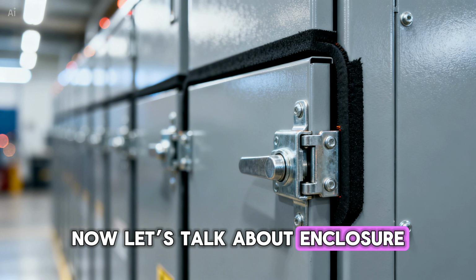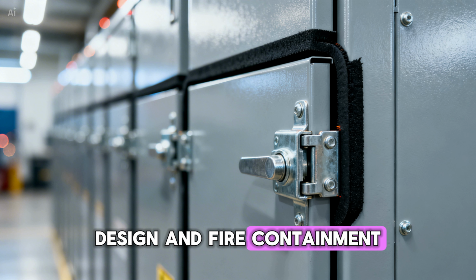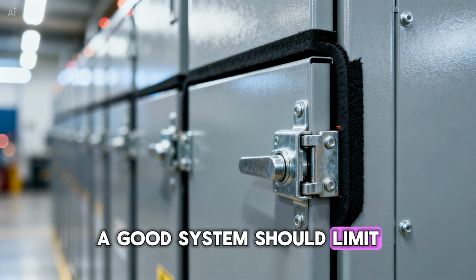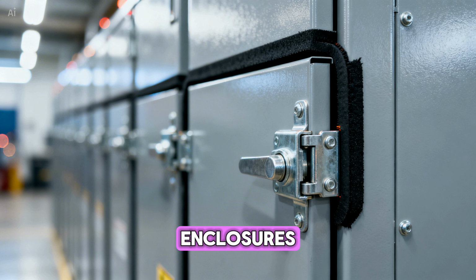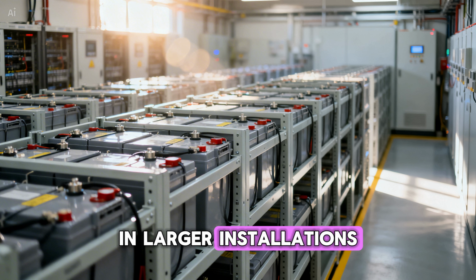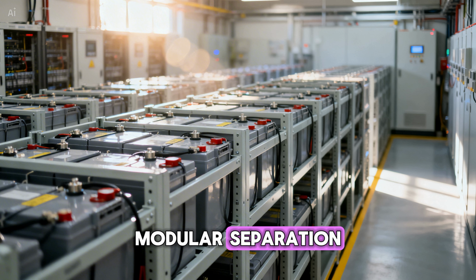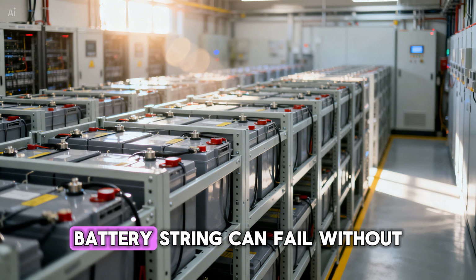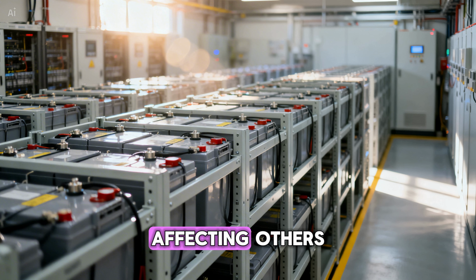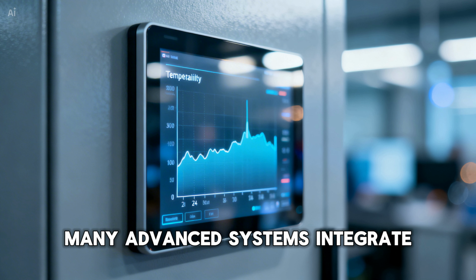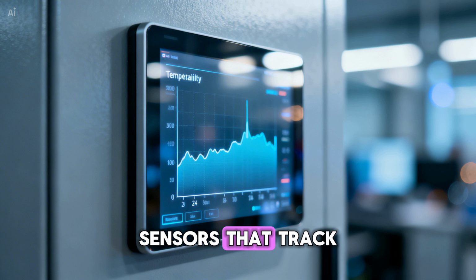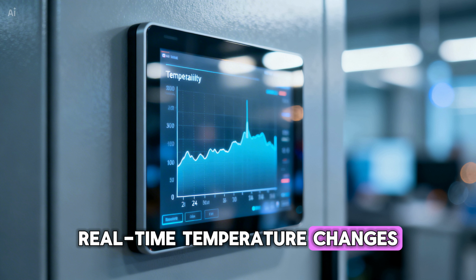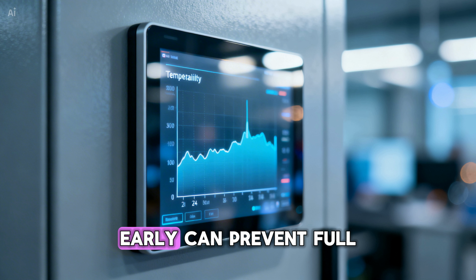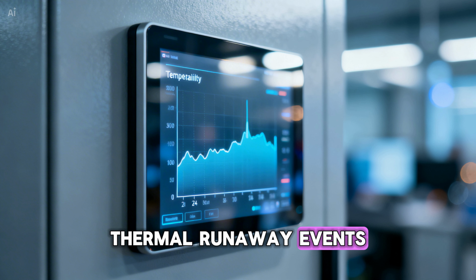Now let's talk about enclosure design and fire containment. A good system should limit damage using fire-resistant enclosures. In larger installations, modular separation is often used so that one battery string can fail without affecting others. Many advanced systems integrate sensors that track real-time temperature changes. Catching spikes early can prevent full thermal runaway events.